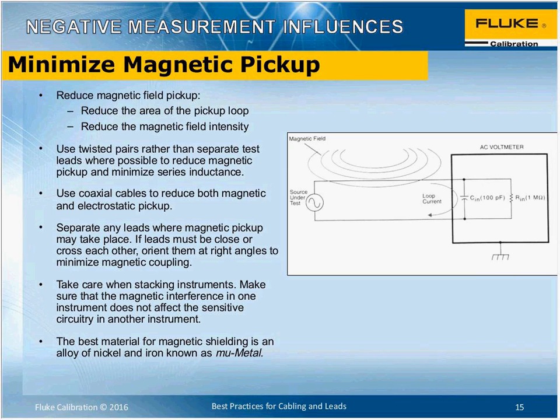Well, as I said, magnetic pickup can be reduced by reducing the area of the pickup loop and by reducing the magnetic field intensity. In other words, take the interferer further away, or reduce it in a way such that you can shield it and so on. Use twisted pairs rather than separate test leads, particularly where there's high current flowing in them. If you twist the leads together, you reduce the radiated effect that might be picked up in some sensitive parts.